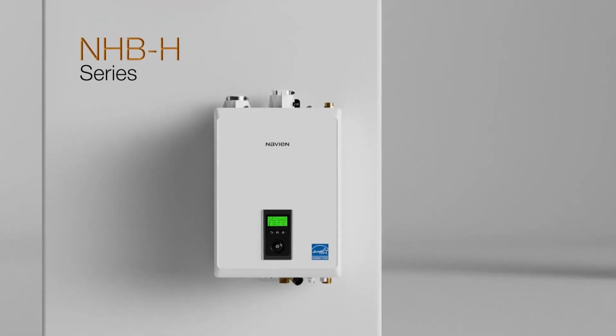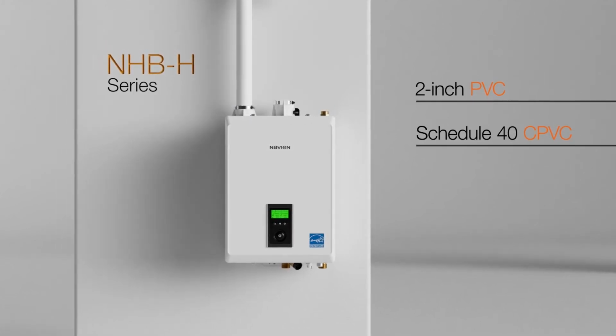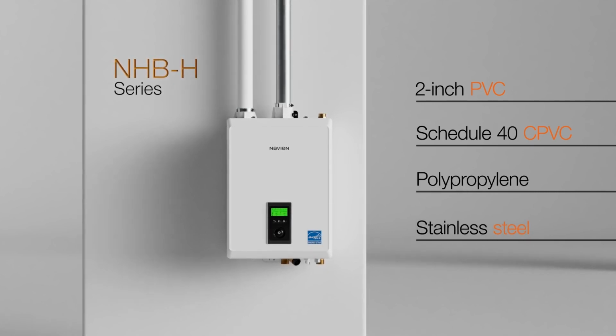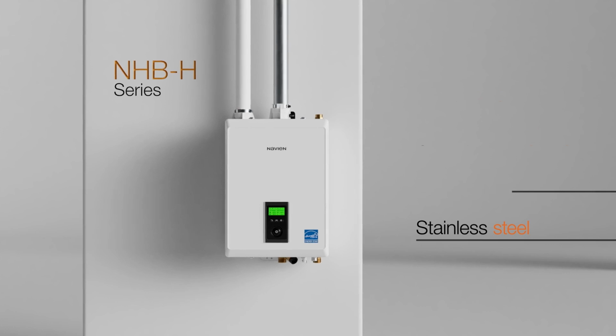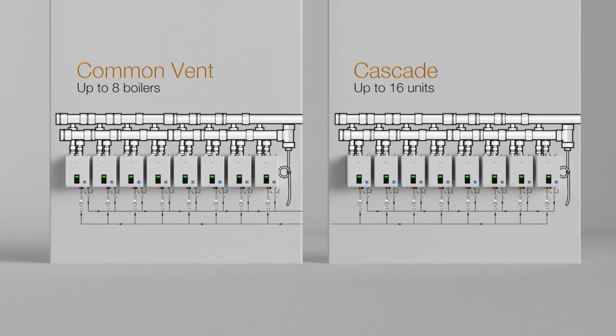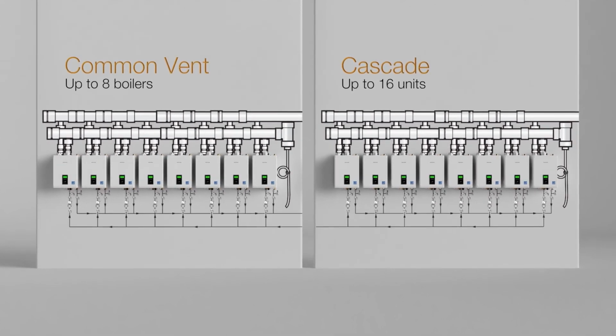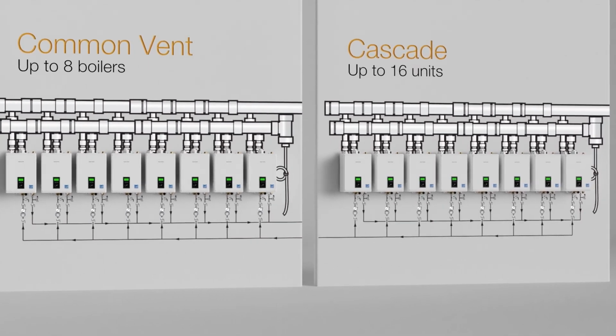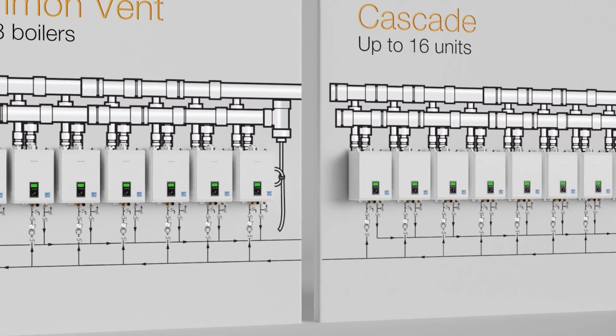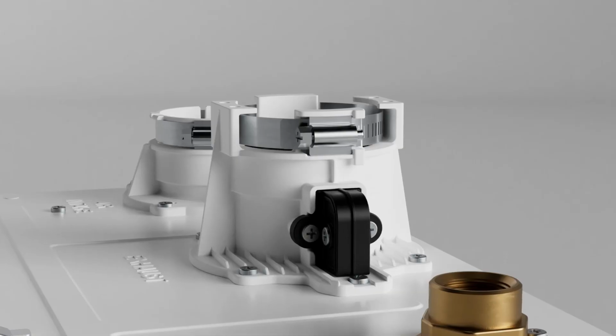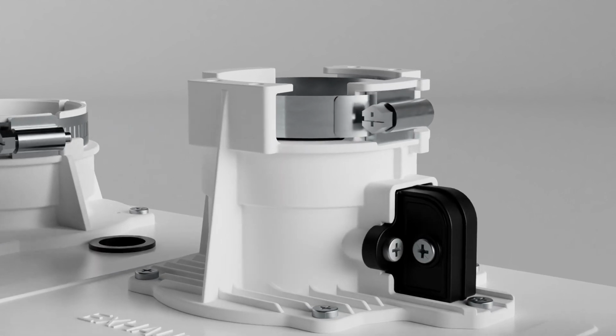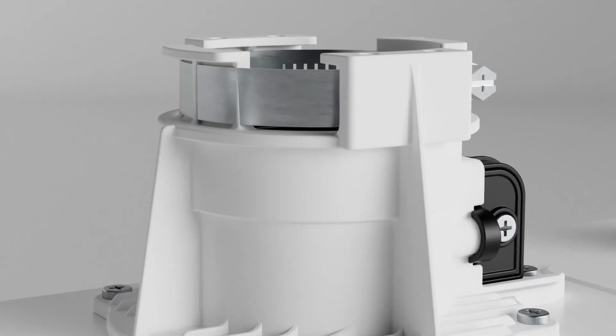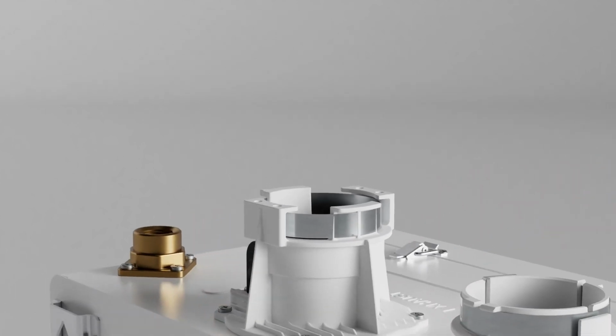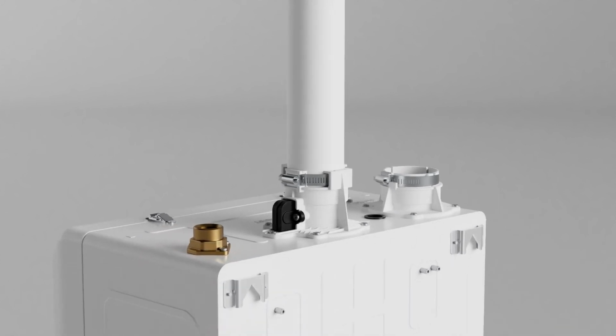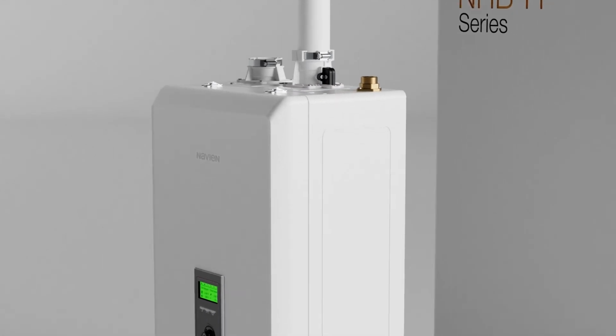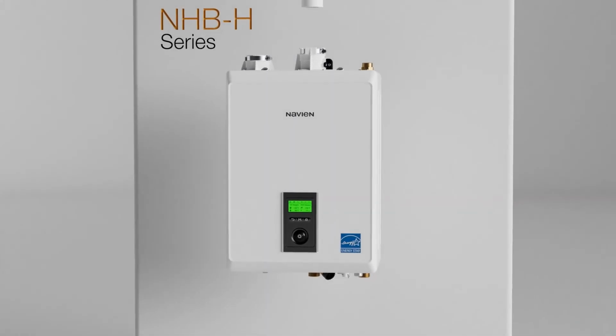The low exhaust temperatures of the condensing NHBH allow use of either 2-inch PVC, Schedule 40 CPVC, polypropylene, or stainless steel up to 65 feet and up to 150 feet for 3-inch. Installers can common vent up to 8 units and cascade up to 16 units when using the NHB110H or NHB150H for greater capacity, reduced venting terminations, and increased turndown ratios. For safe and secure installation, the NHBH comes with a pre-installed vent installation detector, or VID, to support proper vent pipe installation into the vent collar. Connected to the vent collar, the VID detects whether the pipe has been inserted into the collar at a sufficient depth. It also signals improper installation at the time of setup.